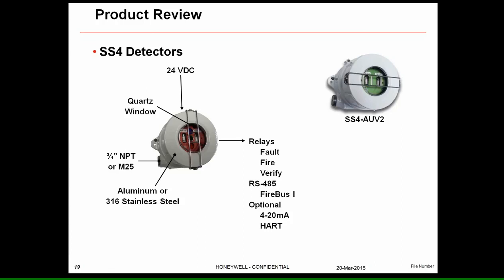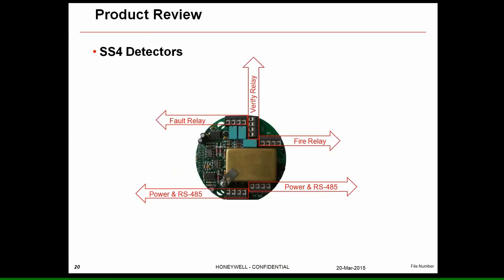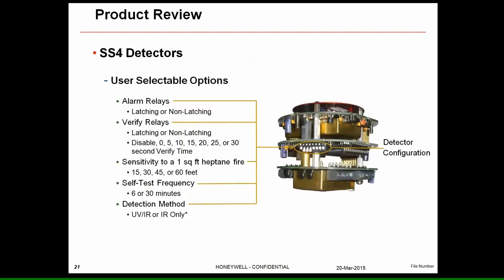The SS4 uses Firebus 1 on RS-485. An optional 4–20 mA card was developed, though it uses the fault and fire contacts to generate the 0 mA fault and 20 mA fire signals. A later HART board mounts to the very bottom of the unit, accesses the Firebus 1 signal, and provides HART over 4–20 mA without consuming any of the relay positions — so you keep all three fault, fire, and verify relays intact. This detector also has a through-the-lens self-check and switch-selectable options.